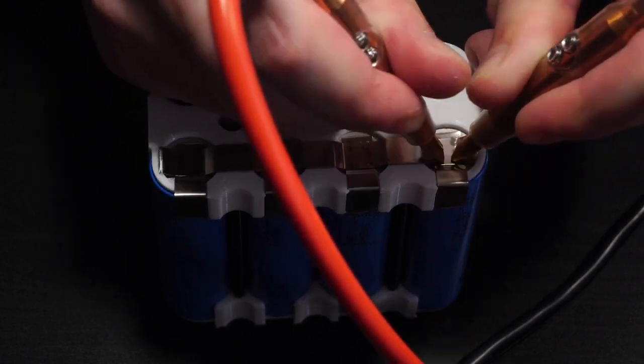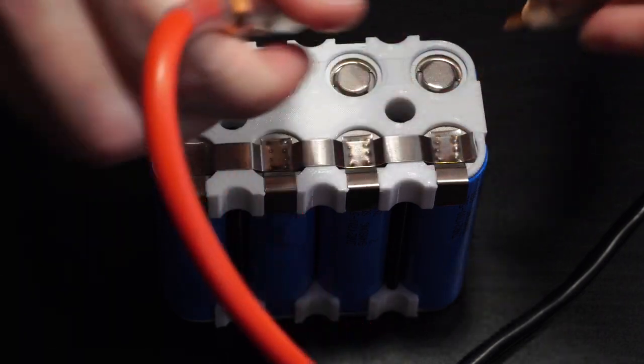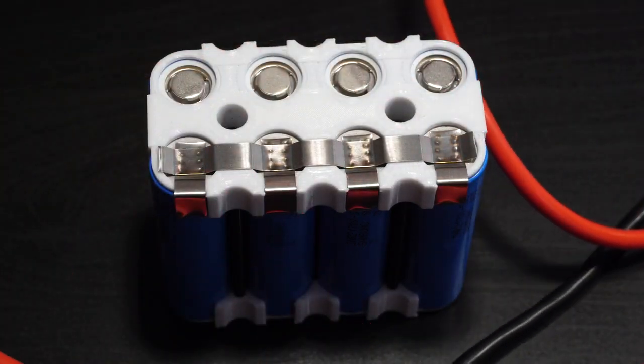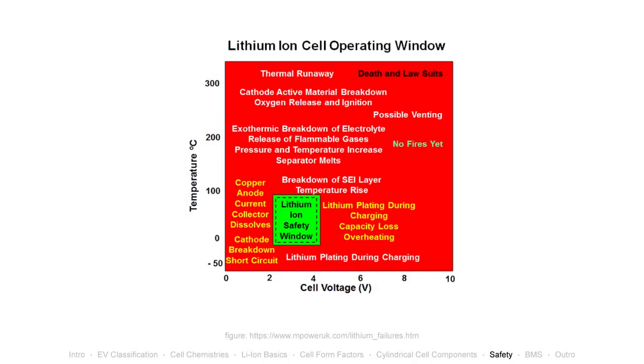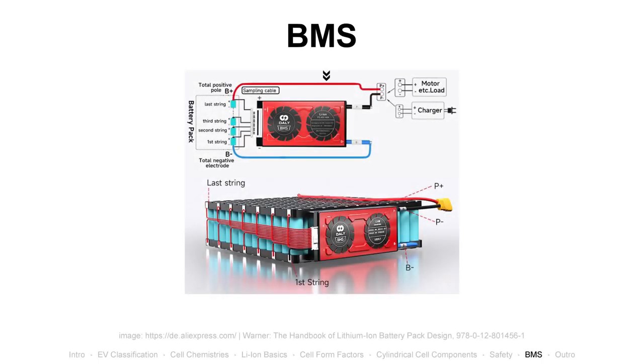While I'm busy doing more than 500 spot welds, let's learn some more about safety. As we've seen, the cell has quite some protection against incorrect usage, but that may not be sufficient in some cases. This leads us to the most critical safety device, but it's not in the cell. The Battery Management System, or in short BMS, has the purpose to enforce the operational limits on the battery. This way, we can keep the cells within their safe operating envelope discussed earlier.